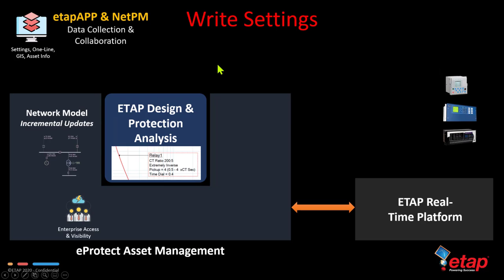So let's take a look at how eProtect is writing the setting file. It may be possible that using ETAP design protection analysis software, you may be changing the coordination settings in ETAP Star or Star Z. And one of the changes could be by just changing the time dial on a particular relay. Note that this is a setting change on a generic relay and not an exact change.